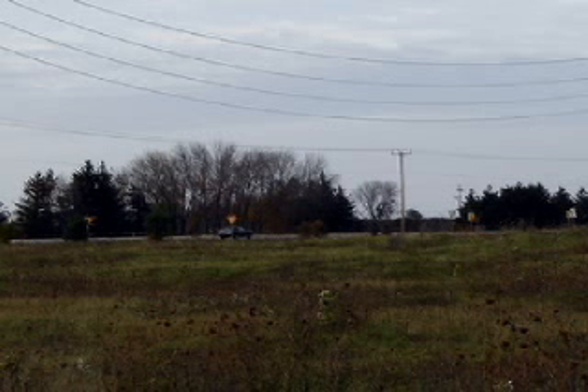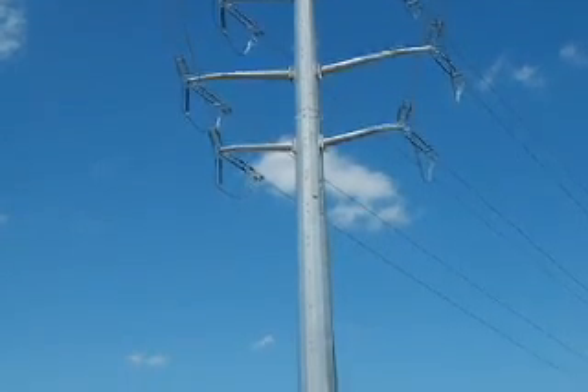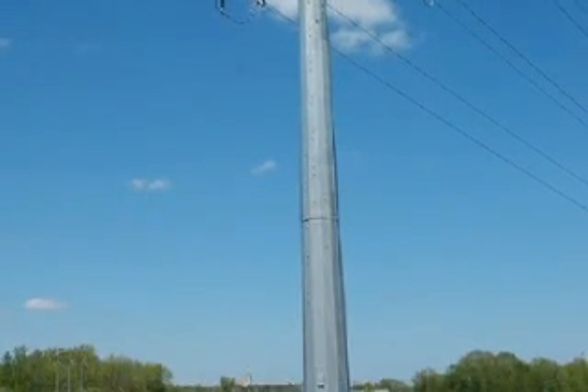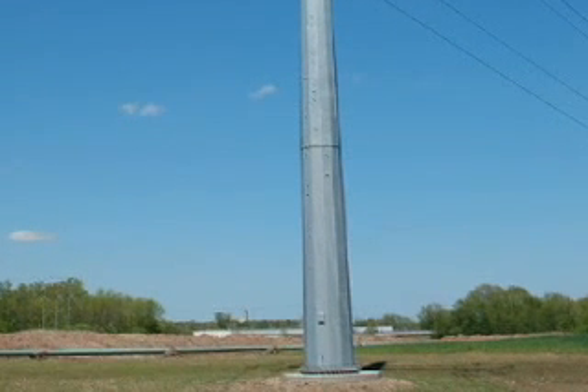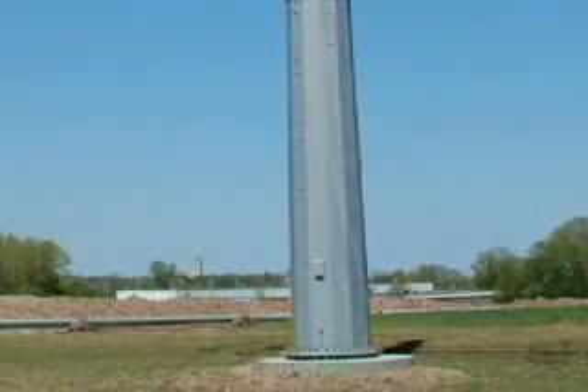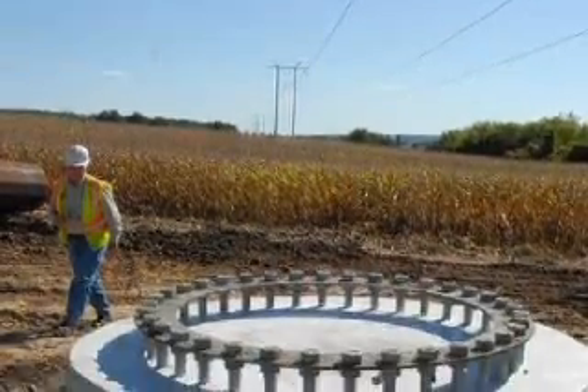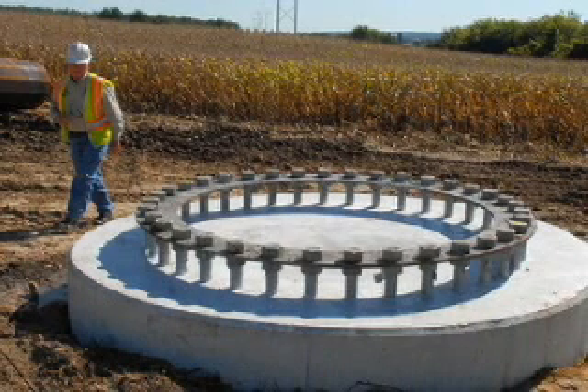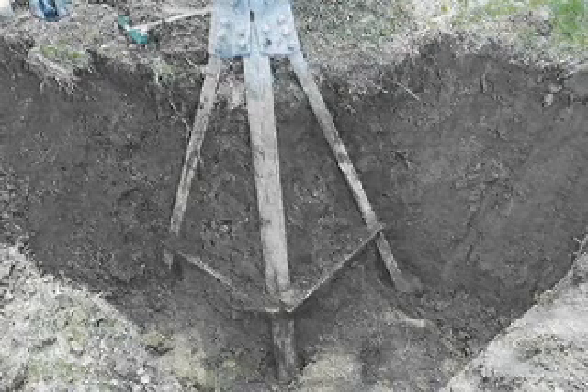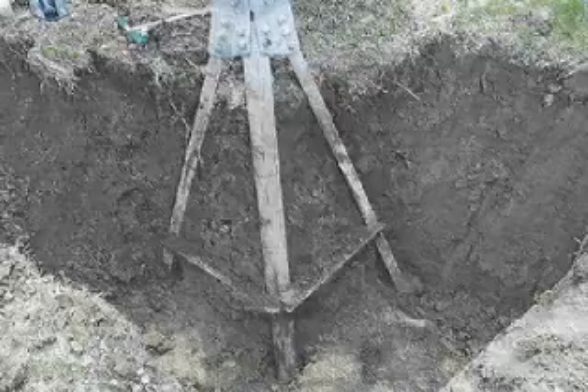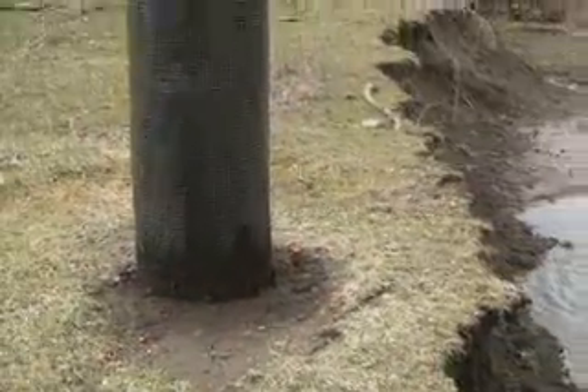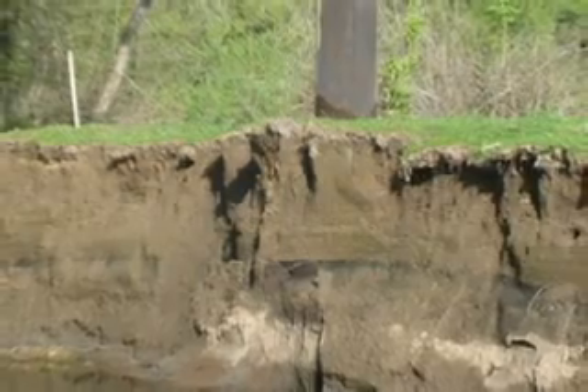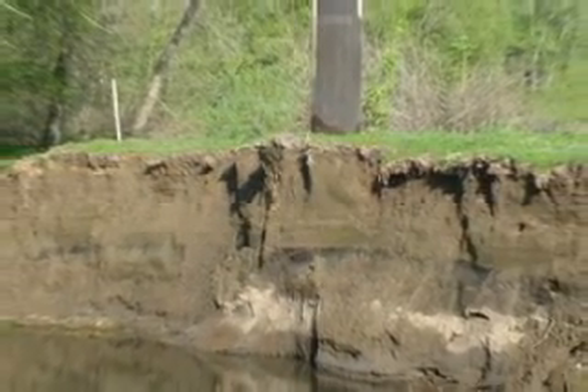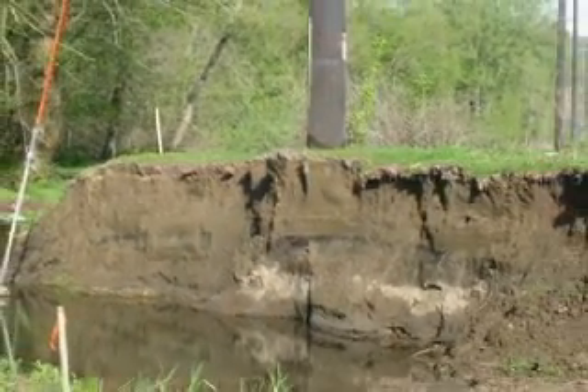Just as working too close to transmission lines can create dangerous and costly mistakes, you must also be careful not to compromise the stability of the structures that suspend the lines. Some transmission structures have massive concrete foundations. Others are buried directly in the ground or have steel anchor foundations. All of these structures rely on the weight of the earth for stability. Removing soil from around the base of a transmission structure can cause the structure to become unstable and fall over. Placing additional fill around the base of a structure can also create problems.